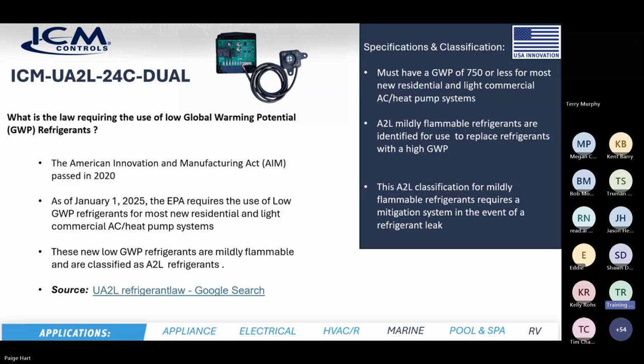As of January 1st, 2025, the EPA now requires the use of low global warming potential refrigerants for most new residential and light commercial HVAC systems. Anytime you're putting in a new system, or upgrading and changing out the whole system, you'll need to go with these new refrigerants. They're classified as A2L refrigerants, and as of 2025 the refrigerant has to have a global warming potential of 750 or less for most new residential and light commercial AC and heat pumps.